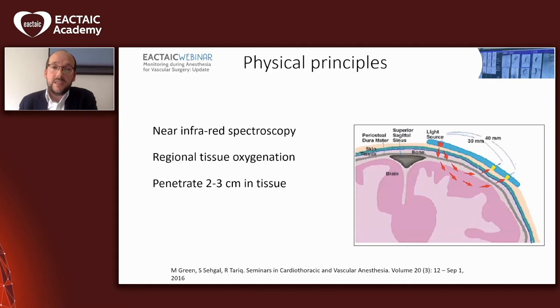Now the physical principles — we need to know a few things about how this monitoring works. NIRS stands for Near Infrared Spectroscopy. As shown in the image on the right, there is a part that emits light and another part that receives the light after it penetrates the tissues. We are measuring oxygenation in this specific area, and we need to remember that the light will only penetrate two to three centimeters, so we can only gather information in the close area where we place our sensors.